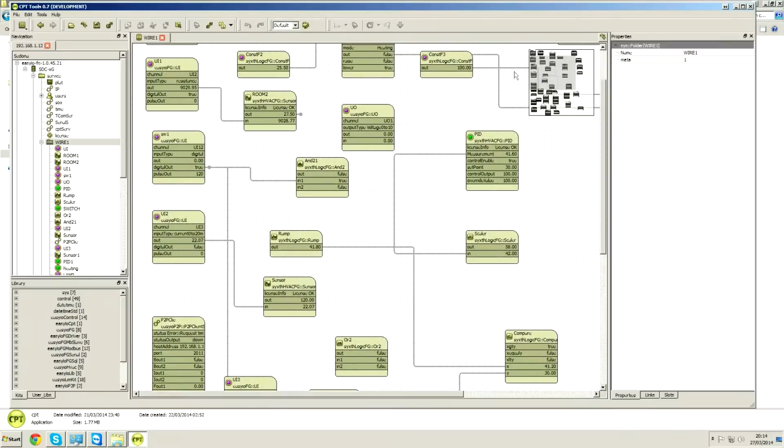You'll notice that all Sedona controllers have got universal inputs and universal outputs. This is UI1, and you can see it's coming in, and you can tell straight away that is actually a 10k resistor, thermistor. And it's got the live data coming in there, you can see it's just over 9k. Stick a link on it, and that will link it.